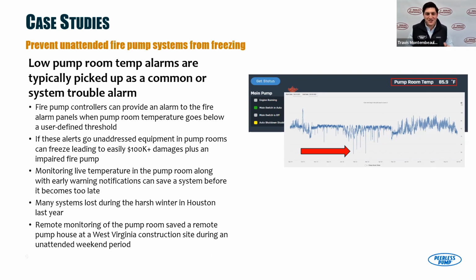Cracked pipe, cracked pumps, could be $100,000 in damages just to that equipment alone in the pump house. But then you think of the real cost: what would that mean for the construction if this was providing temporary fire protection for that site and they weren't able to operate? What would the implications of that be? So this system effectively paid for itself 3-4 weeks into being installed, because he couldn't be there 24/7 on a Saturday to look for the alarm, but the system told him when there was an issue. We're trying to get proactive and avoid these situations before they become major situations, so we're trying to head them off.